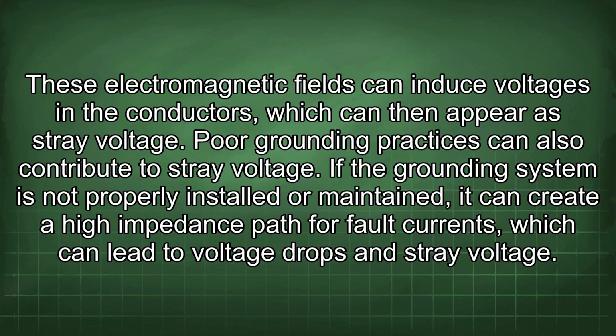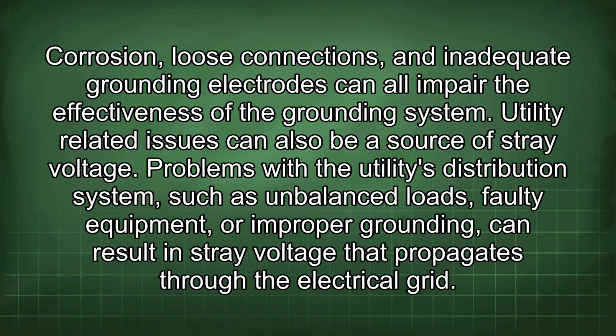Poor grounding practices can also contribute to stray voltage. If the grounding system is not properly installed or maintained, it can create a high impedance path for fault currents, which can lead to voltage drops and stray voltage. Corrosion, loose connections, and inadequate grounding electrodes can all impair the effectiveness of the grounding system.